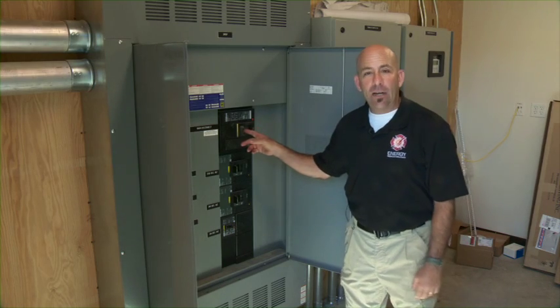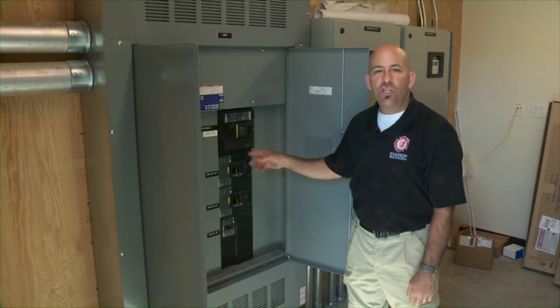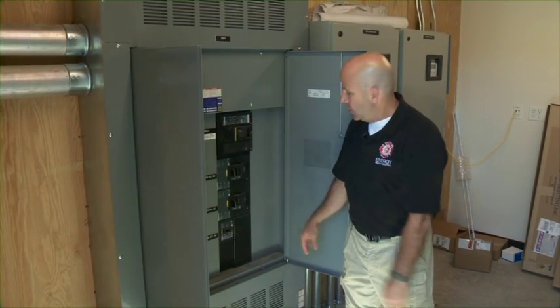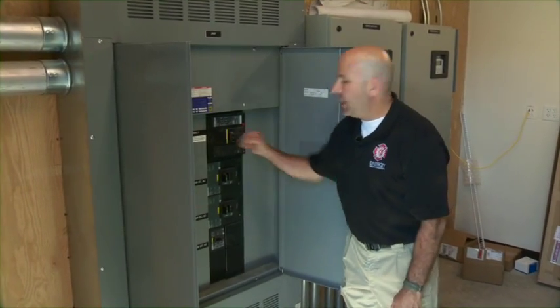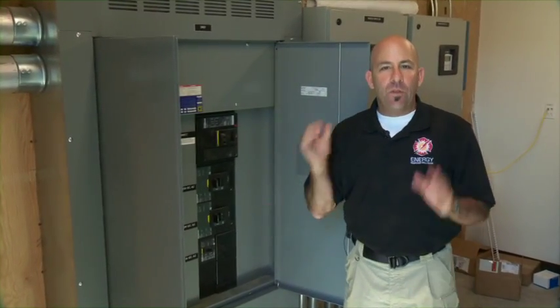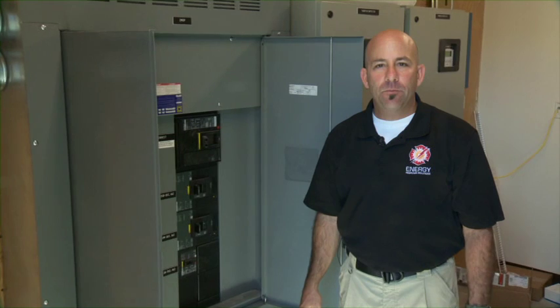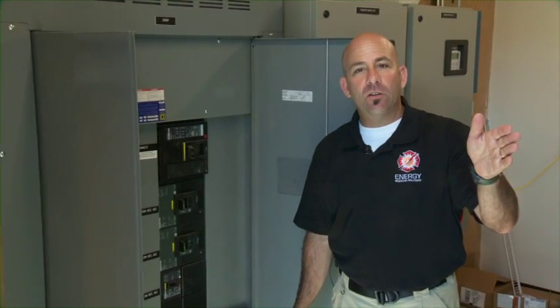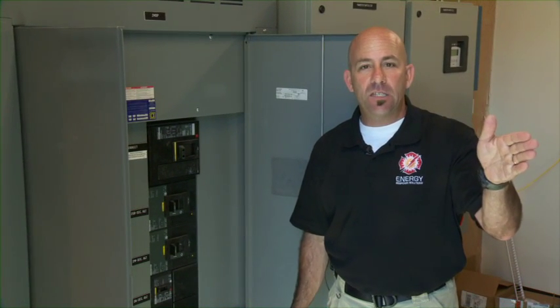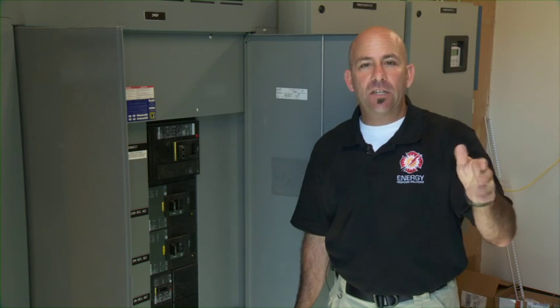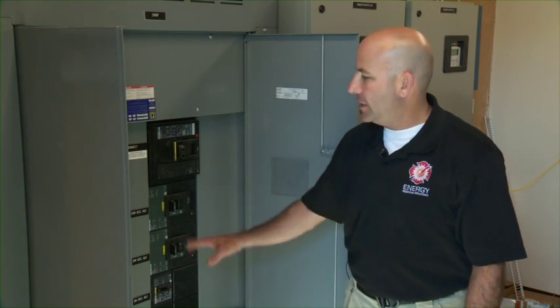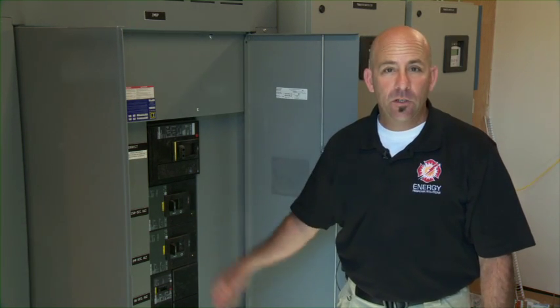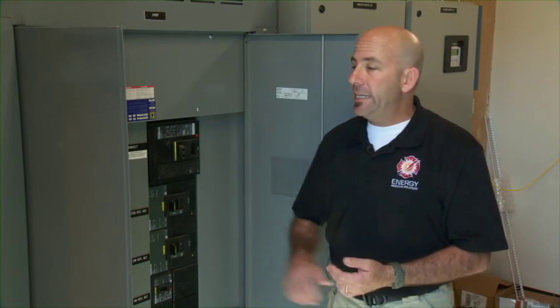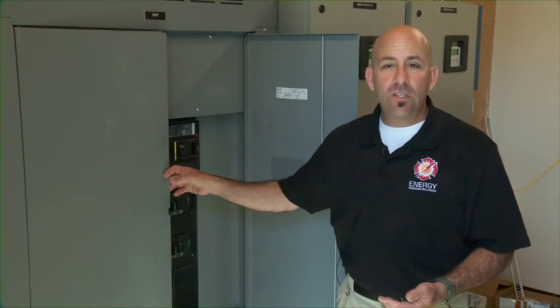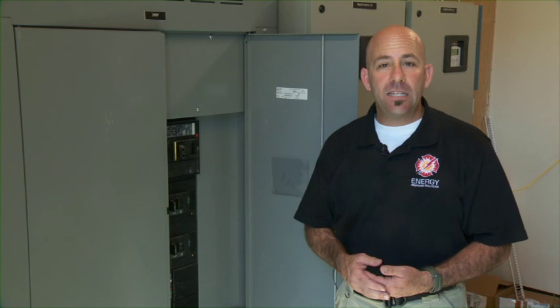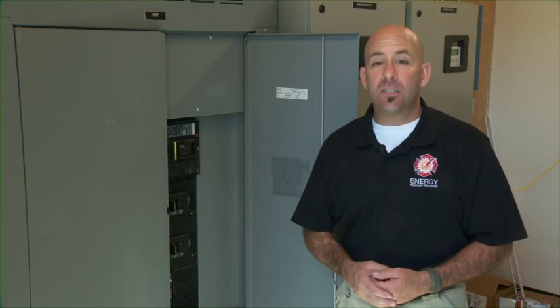Here we've got an 800 amp breaker. It's a good idea to shut down the small ones first. Just go ahead and shut each of these off and then shut off the main one. That will take off the PV system. But we had found the AC disconnect outside for the PV system. So in this particular case, it's only outside. There's nothing in here for it, at least not labeled. The other thing, there's no label in here that talks about who installed the system. So if you need to contact somebody, we're going to be a little lost in this particular system.